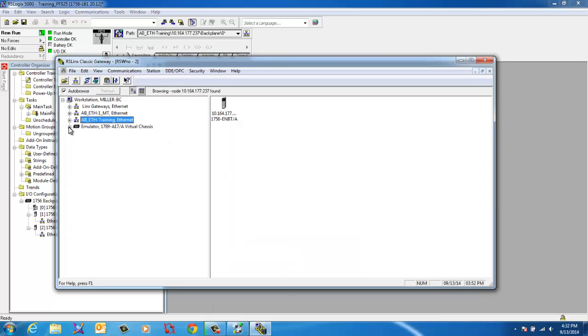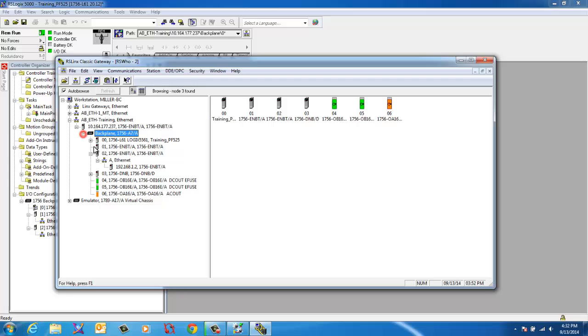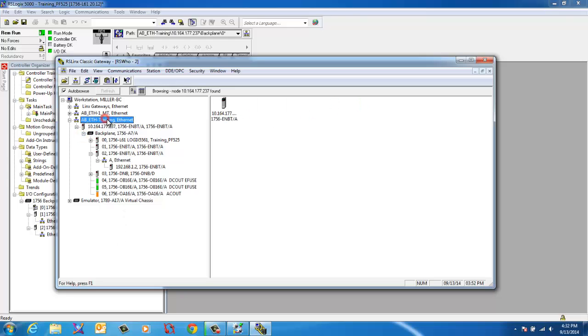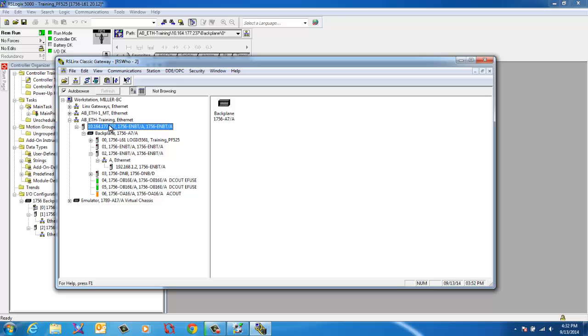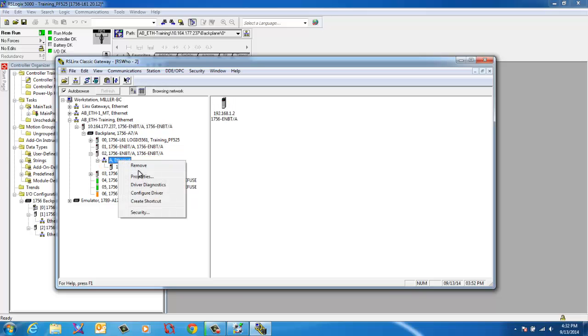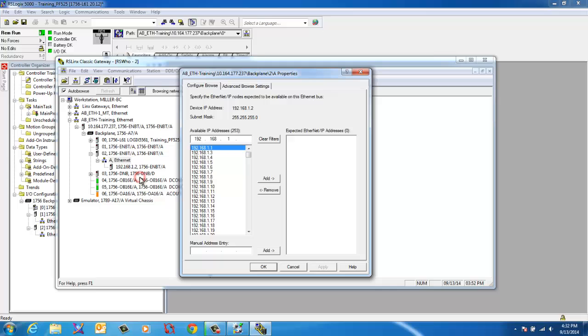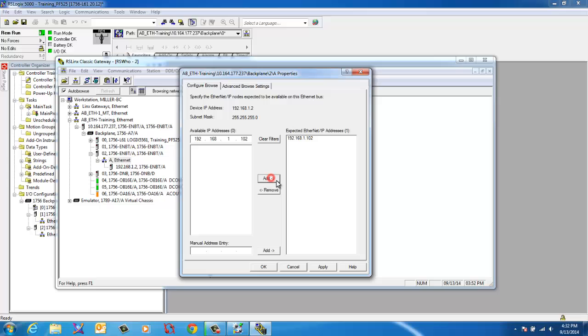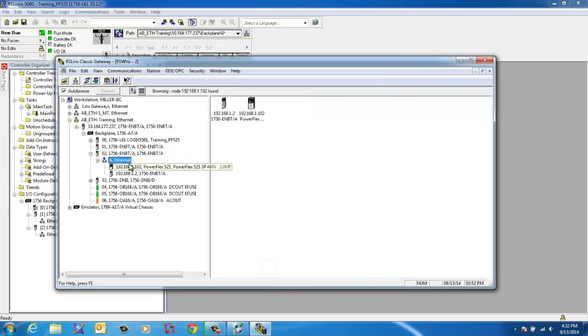So we're going to go ahead and come over and we're going to add it to our processor. As you can tell I've already added this IP address in. If you want I can back up and go through and re-add everything so you can see how we found it. But we added two cards. And that is of course the first ethernet card which we call the automation network and then the second one which is our private network. What we're going to do is we're going to properties. Now the drive that I set up has an IP address of 192.168.1.102. So we're going to use that drive. We're going to hit apply. We're going to hit ok. Populates the list. Here's your 525. It just populated. It's online. We see it.